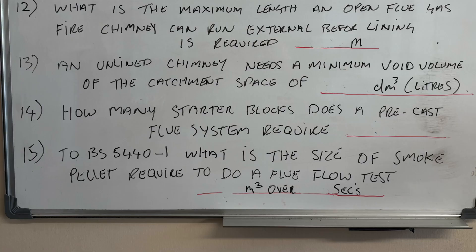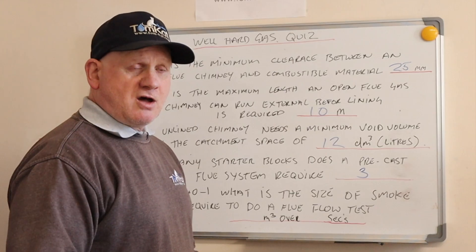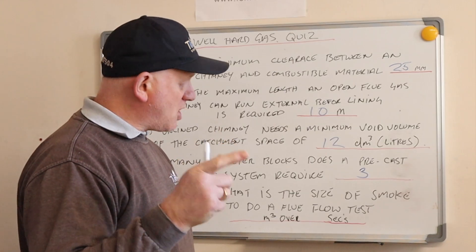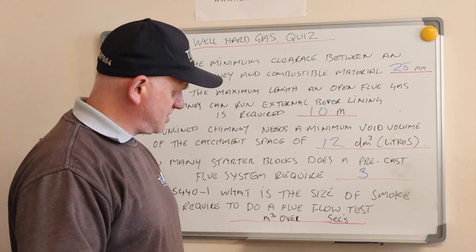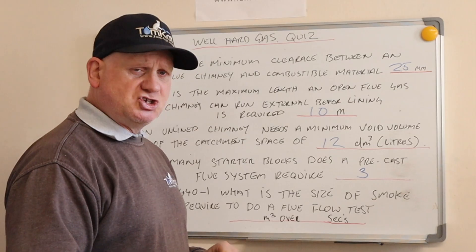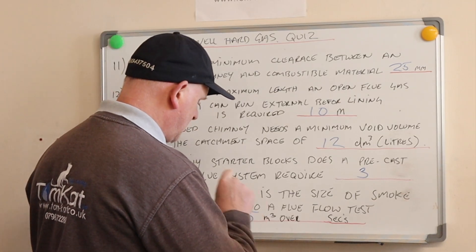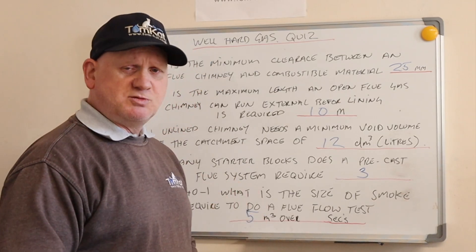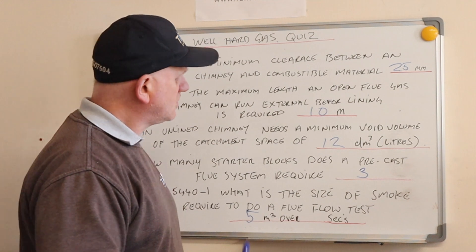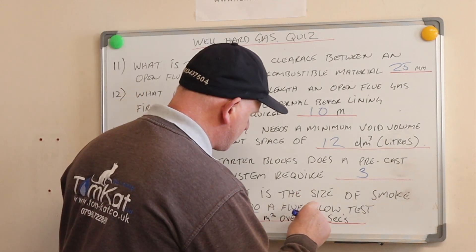Question number fifteen: to BS 5440 part one, what size smoke pellet is required to do a flue flow test? It needs to produce five meters cubed of smoke over thirty seconds.